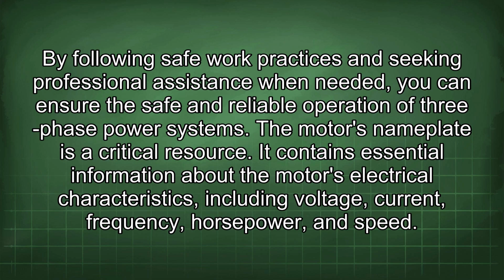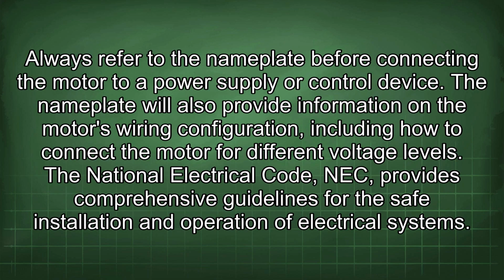The motor's nameplate is a critical resource. It contains essential information about the motor's electrical characteristics, including voltage, current, frequency, horsepower, and speed. Always refer to the nameplate before connecting the motor to a power supply or control device. The nameplate will also provide information on the motor's wiring configuration, including how to connect the motor for different voltage levels. The National Electrical Code (NEC) provides comprehensive guidelines for the safe installation and operation of electrical systems.